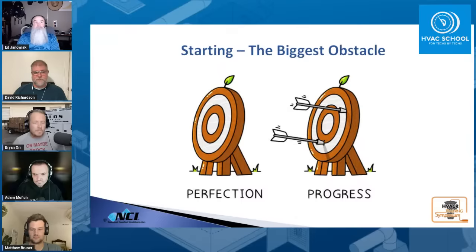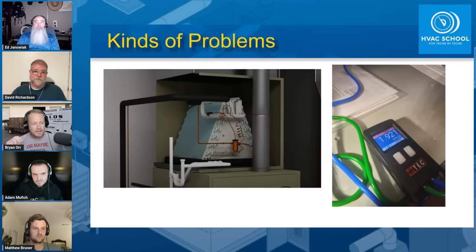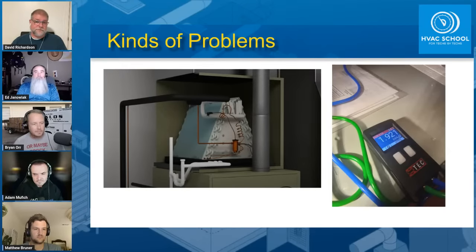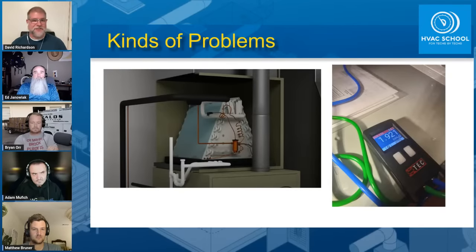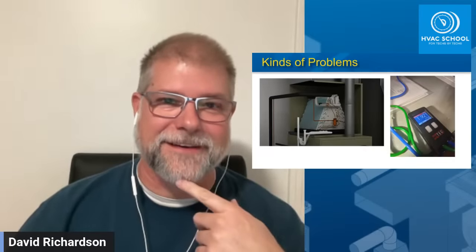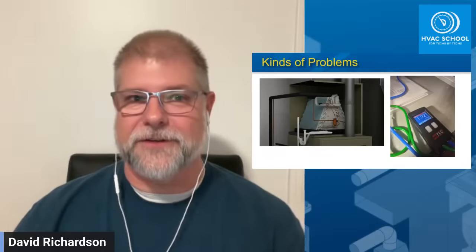When looking for indicators of potential problems, a lot of people want to jump straight to measurements. But measurements should verify what you already know. Ed mentioned Manual D — if you follow those principles and look at fittings, you can see right away what's right or wrong. It always starts with the visual inspection: take the doors off the equipment and look at it. You can identify a lot without test instruments, but you do need instruments to quantify it — otherwise, it's just opinion.